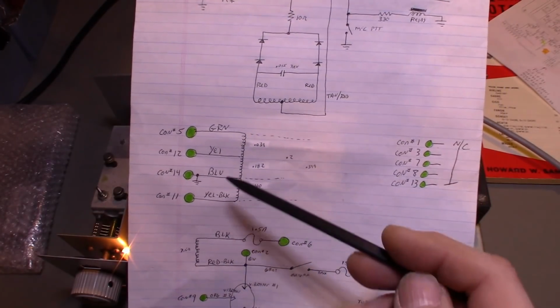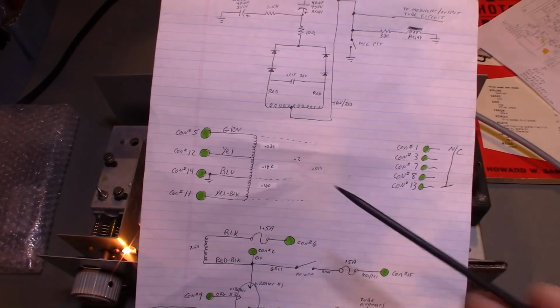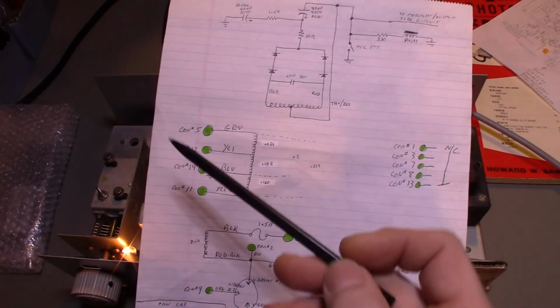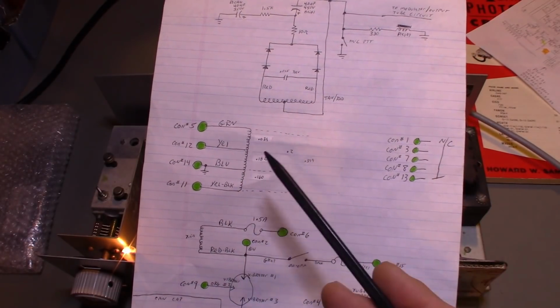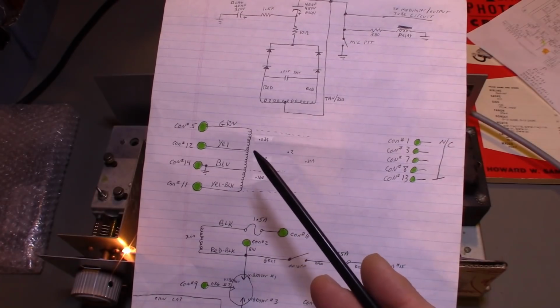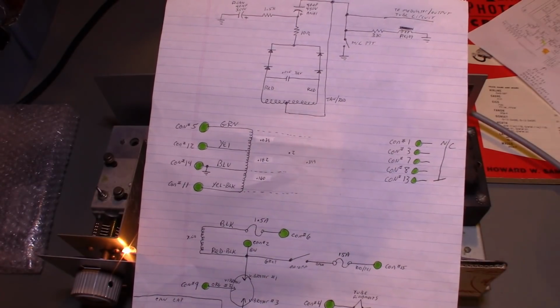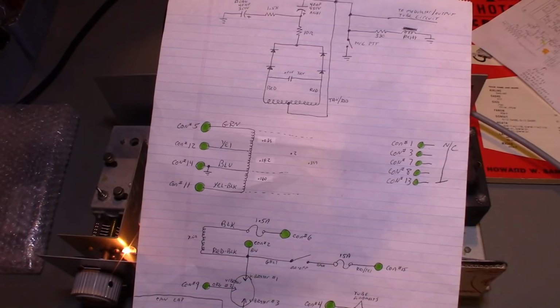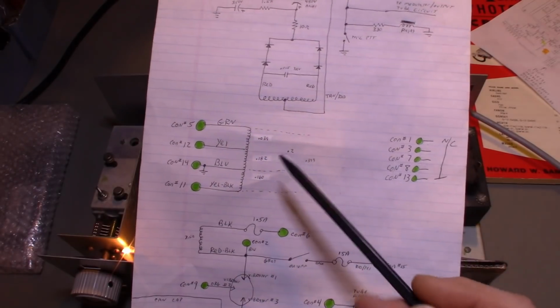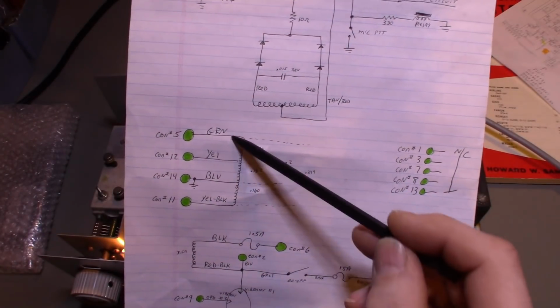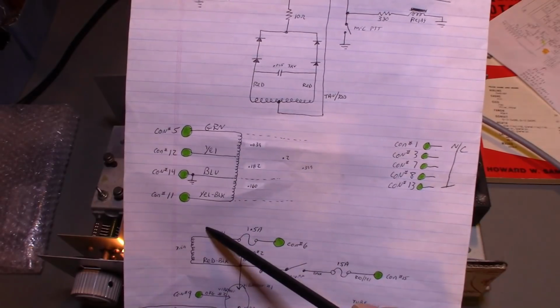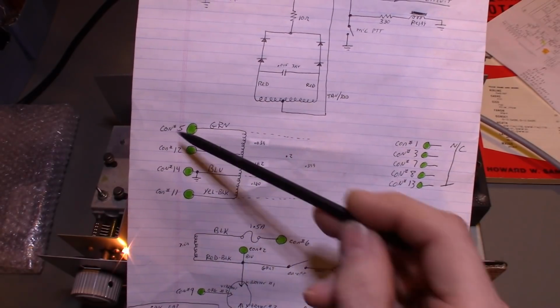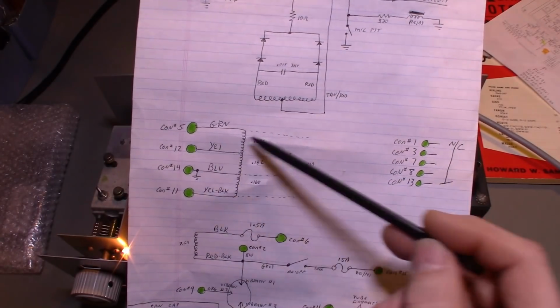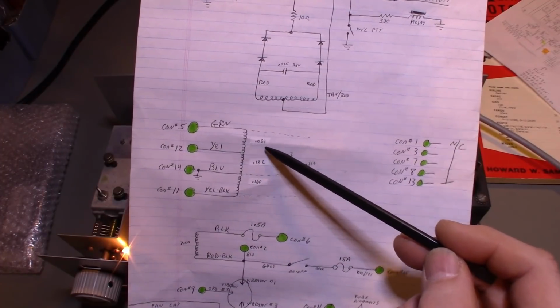The easiest way to do that is if you have a very accurate ohm meter. I'm usually using either a 5.5 or 6.5 digit multimeter, so it measures way down into sub-ohm readings. With a good set of Kelvin clips, you can take very precise resistance measurements and figure out what the windings are, because between contact 5 and 12 I had 0.039 ohms.